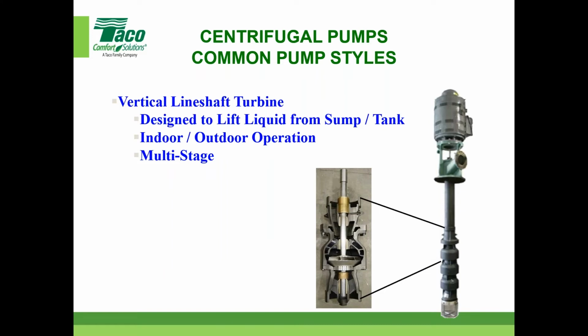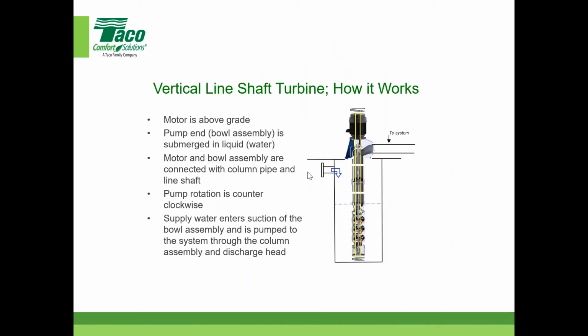We also have vertical line shaft turbine pumps. All the other pumps we've discussed need a flooded suction in order to operate correctly, but these can actually lift the water—so if you have a sump application, they can lift the water up. Taco has a vertical turbine offering for HVAC, as well as for industrial wastewater, municipal, or farming type projects—a complete line. That's a whole different setup, and they're actually manufactured in different parts of the United States, not in Cranston. To show how it works: the water goes in here, flows through, is sucked up through these bowls, and out to the system.